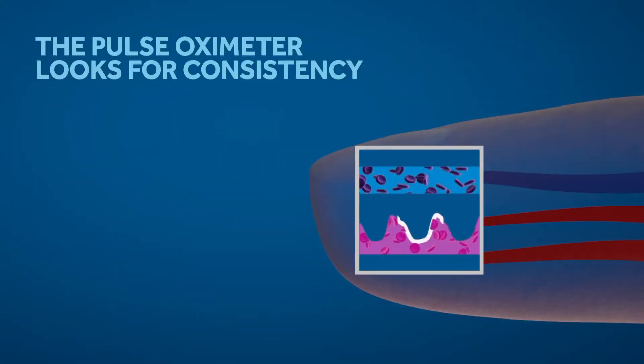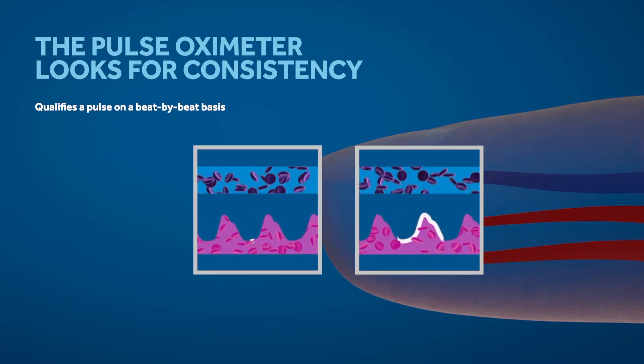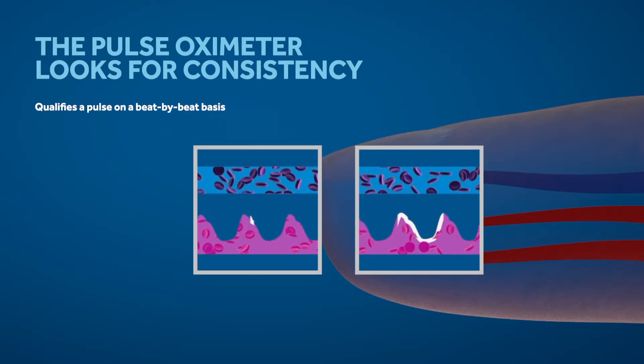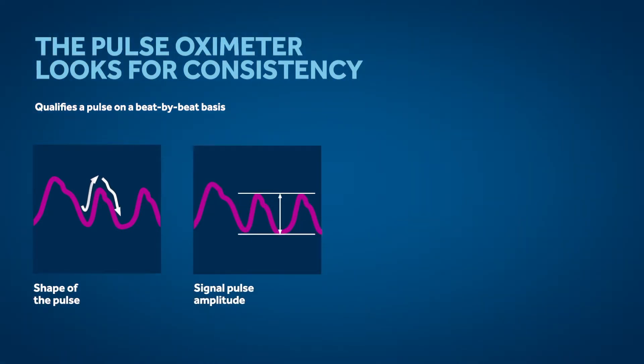Nellcor pulse oximetry technology identifies and qualifies a pulse on a beat-by-beat basis. The pulse oximeter looks for consistency in the shape of the pulses including signal pulse amplitude or height of the pulse and the frequency of the pulses.